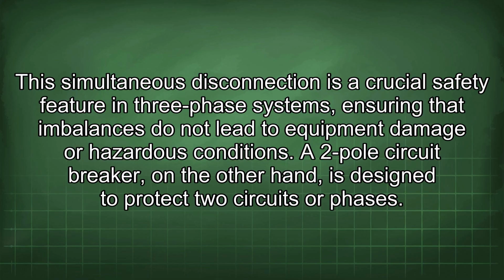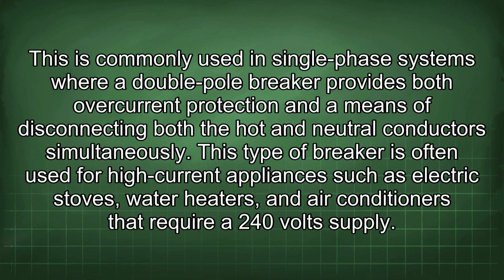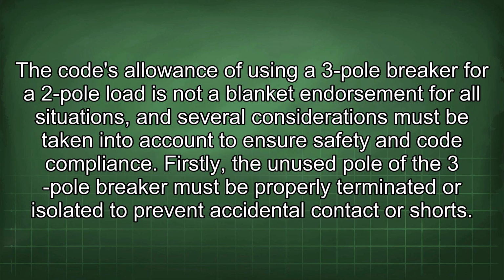A 2-pole circuit breaker, on the other hand, is designed to protect 2 circuits or phases. This is commonly used in single-phase systems where a double-pole breaker provides both overcurrent protection and a means of disconnecting both the hot and neutral conductors simultaneously. This type of breaker is often used for high-current appliances such as electric stoves, water heaters, and air conditioners that require a 240-volt supply.